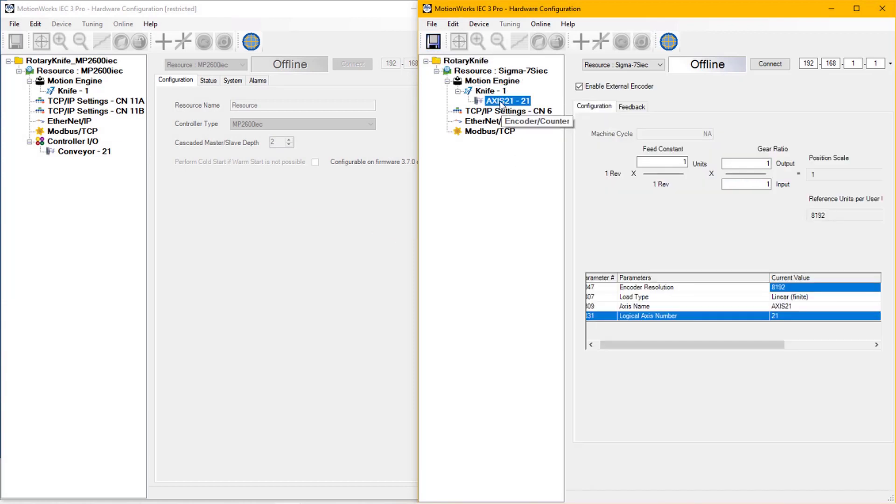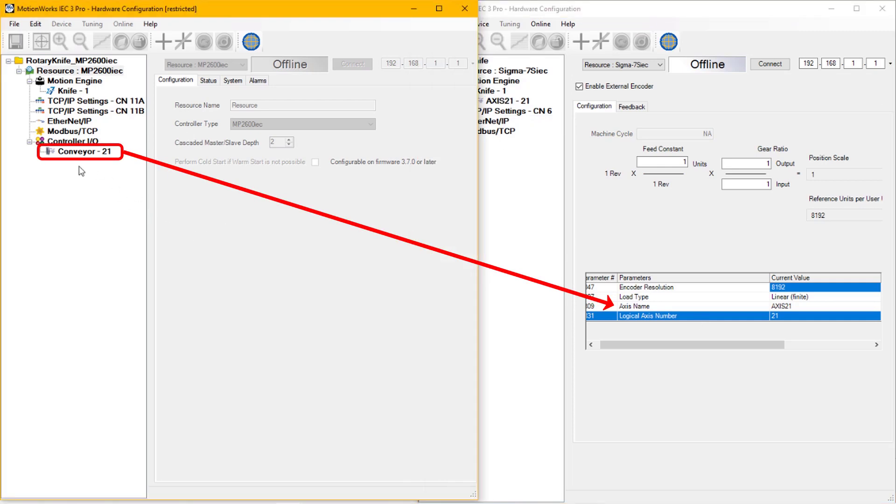External encoder moves in forward direction for counter-clockwise motor rotation. Axis 21 is now available under the knife axis in the hardware window. At this point, I can do a quick offline save, and now Axis 21 needs to be set to the same name that's used inside the MP2600 IEC project, which is Conveyor.